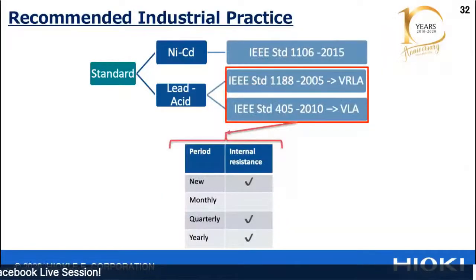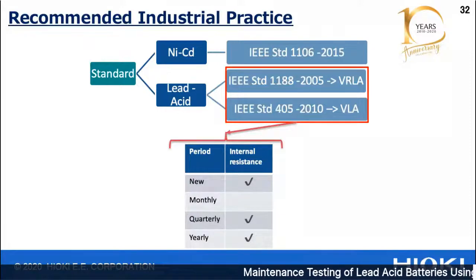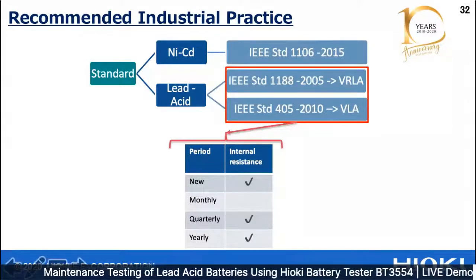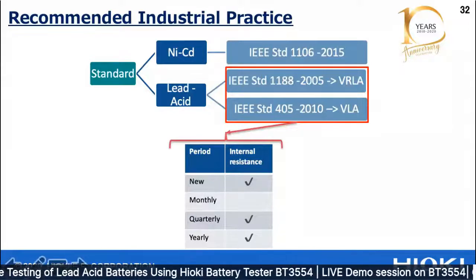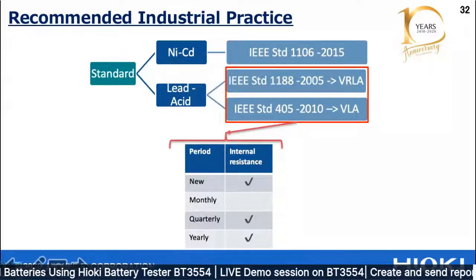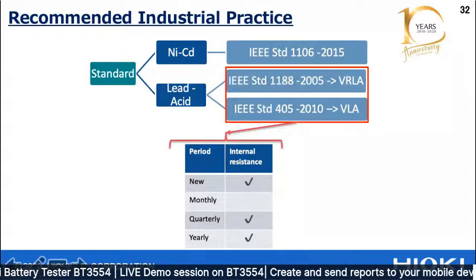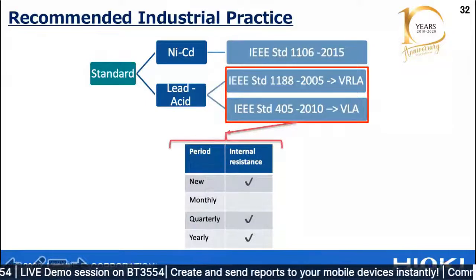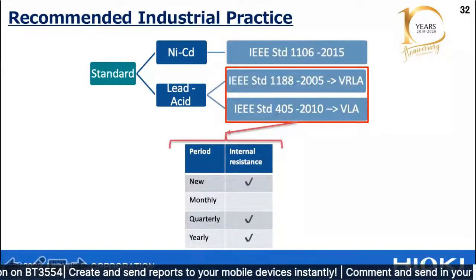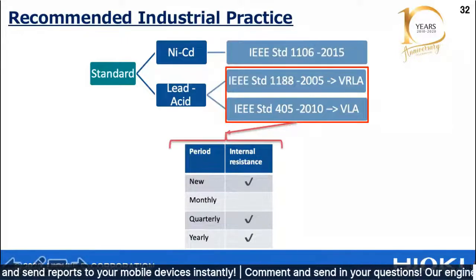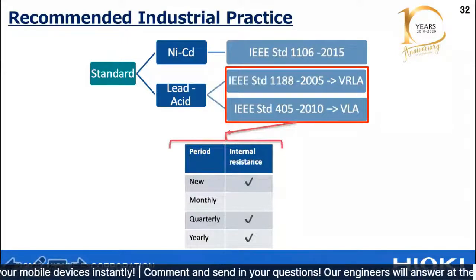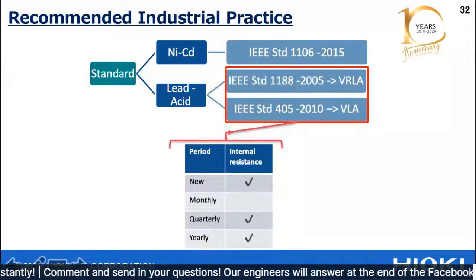Now I'll talk about industrial practice - these are the standards to follow with regard to different types of batteries. For nickel cadmium, you can follow IEEE standard 1106. For lead acid battery, you can follow standard 1188 - this is for valve regulated lead acid. And you can follow standard 405 for vented lead acid type.